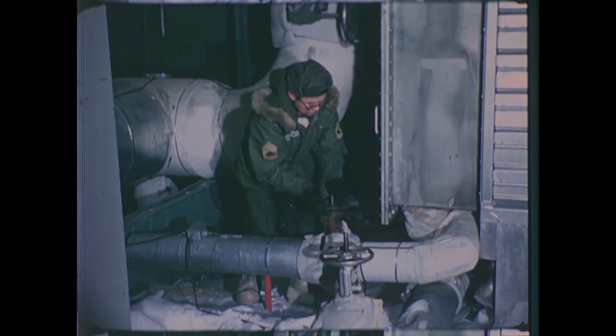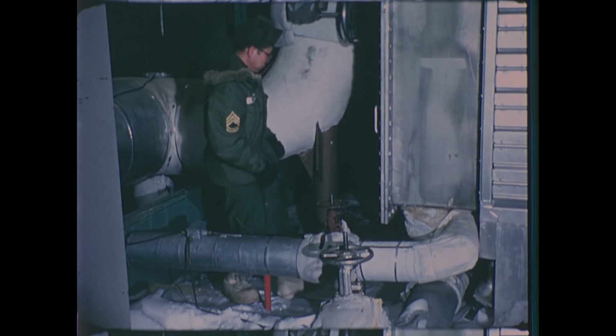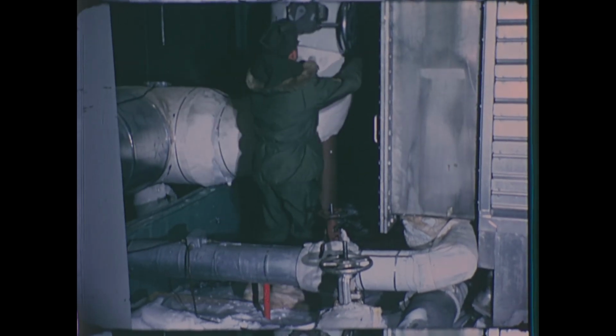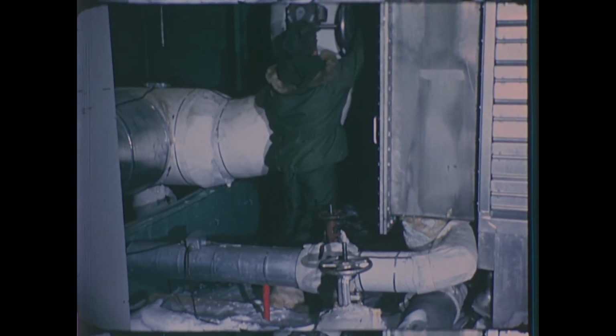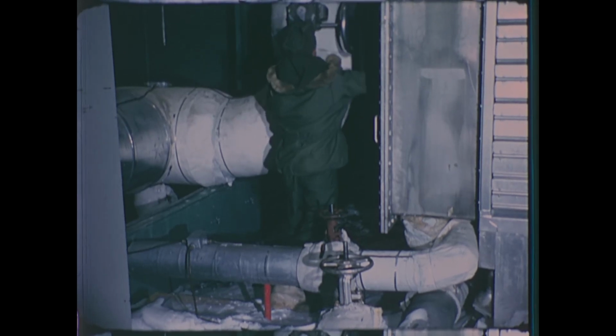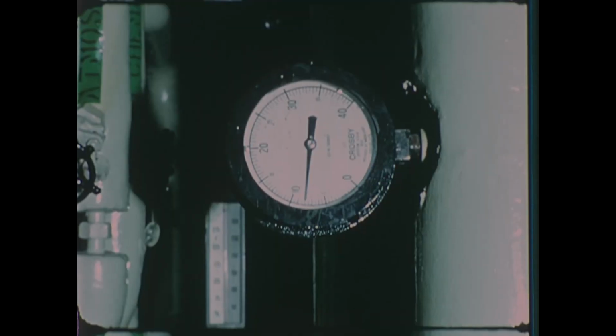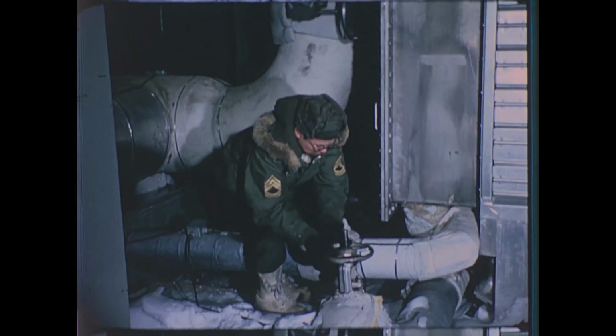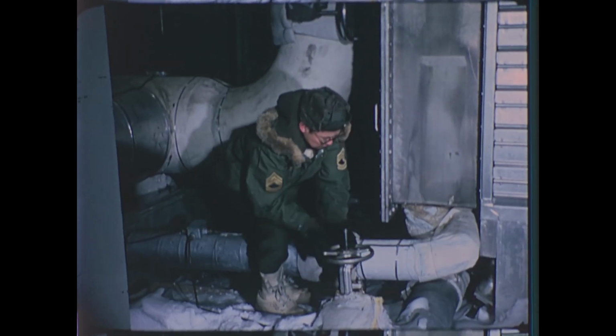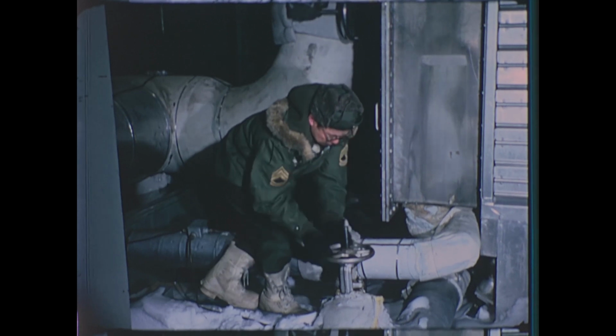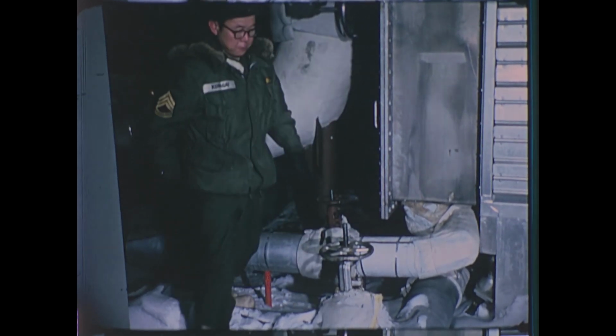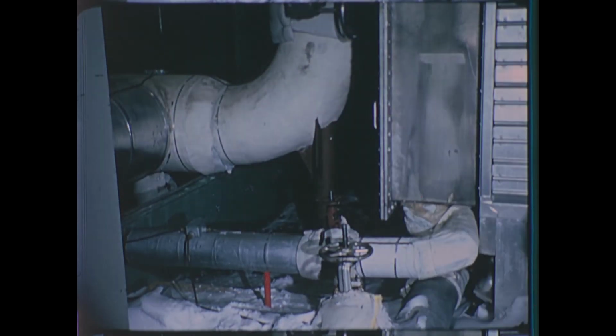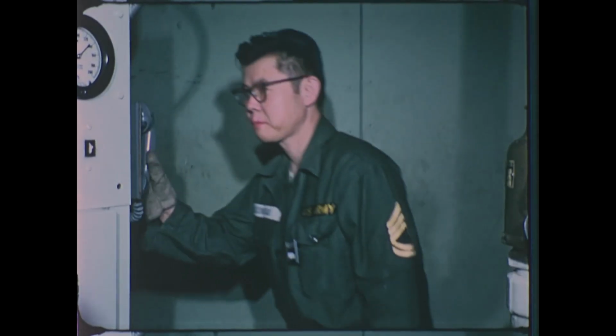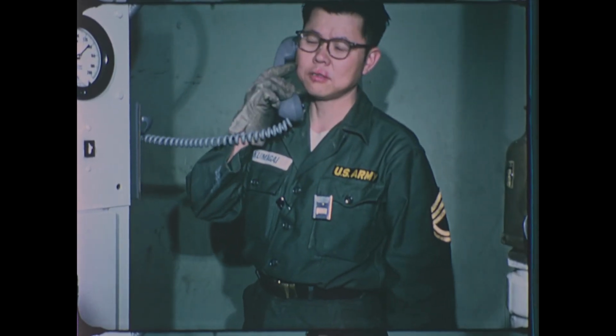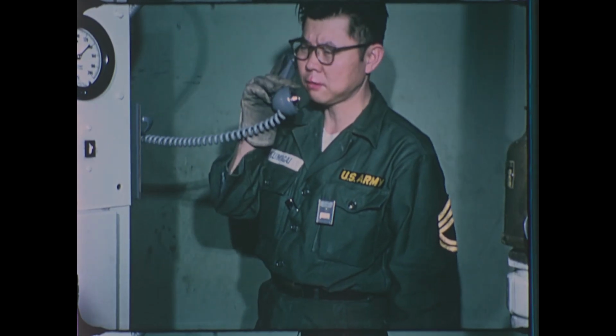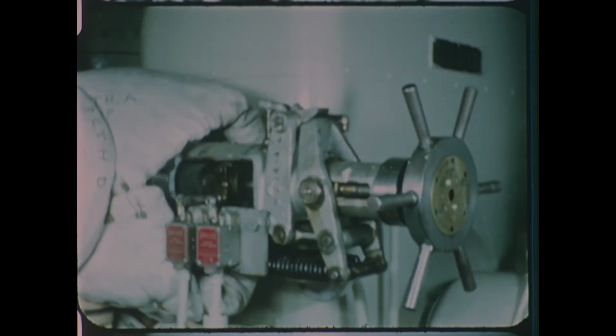He opens valves to the condenser, opens the turbine exhaust steam inlet valve to evacuate air from the system, and opens the condensate return valve to the hot well. With vacuum established in the turbine exhaust system, the equipment operator notifies the control room that he's ready to roll the turbine by opening the turbine throttle valve.